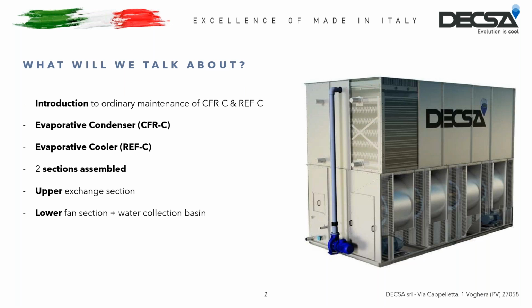This is because some periodic activities require more than just one annual intervention. For example, the greasing of the bearings must be carried out every 4 months or 3,000 operating hours. Same goes for the control of the belts. I remind you that these activities take about an hour per unit, and in the meantime, the inlet water system can remain operating to maintain a partial refrigeration.